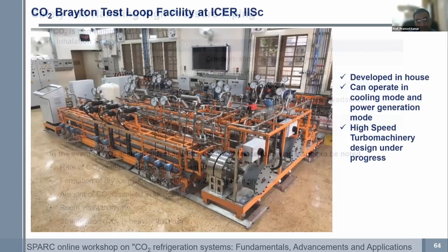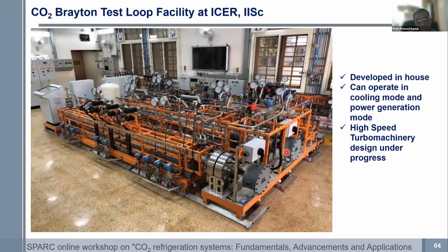Okay, so this is a test loop that we built in 2015 or 16. It is primarily meant for power generation, but it also works in refrigeration mode. And in the last 5 or 6 years, we have never had a single leakage issue in the system, and it has worked very robustly. But as I said, you have to build it right in the beginning, when you build the system.